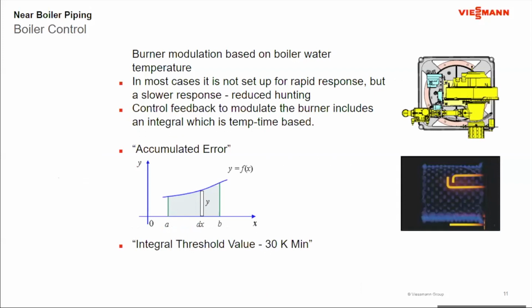Now, the other thing that we have to consider is how we are controlling the boiler. When we look at boiler control, I look at modulating the burner, because the burner is where I'm going to balance the input to the load of the building. I'm going to change the firing rate of that burner. That burner's modulation is going to be based on outlet water temperature.